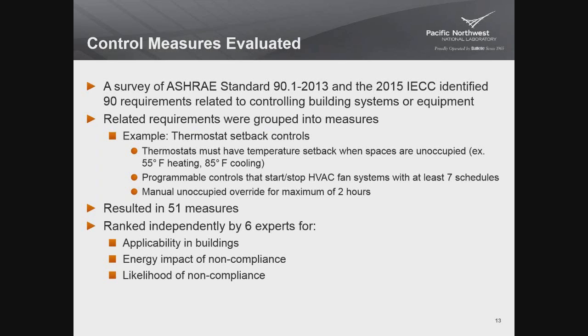And then finally, there has to be a manual override so that if somebody comes in at night, they don't have to turn the whole system on in the whole building and maybe forget about it and leave it on all the time. Instead, it has to have a manual override like a push button that sets the building to occupied status for no more than 2 hours so that it automatically goes back to unoccupied status after that. So those 3 requirements became the thermostat setback control requirement.